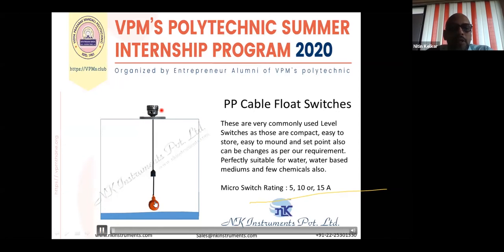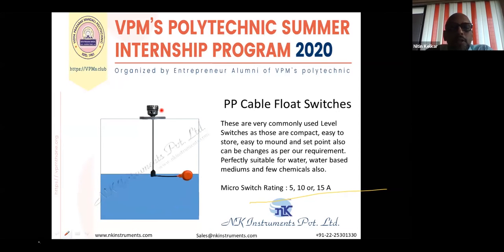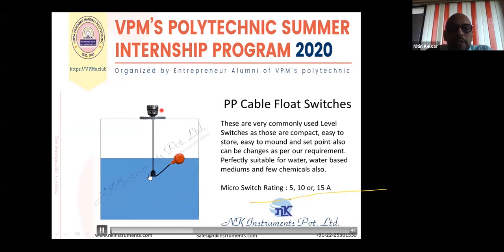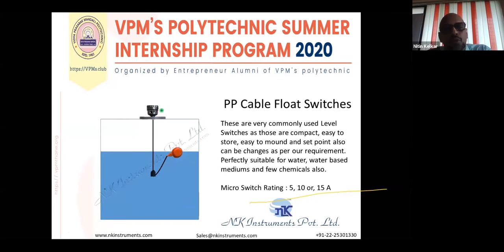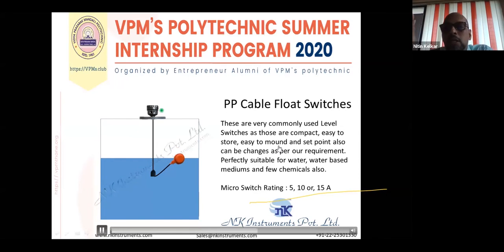It has a float having one metallic ball in it, and at this square portion here there is a micro switch. When the level rises, the float starts floating, and depending on the weight which is connected here, that position we can adjust. If I have set this weight over here, it will not allow the wire to go further upward, and this float will now go in the reverse direction. It will go top side bottom, bottom side top. Now here the switch is operated because that ball touches the micro switch and the switch operates.